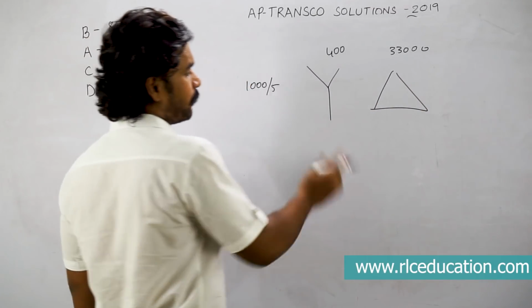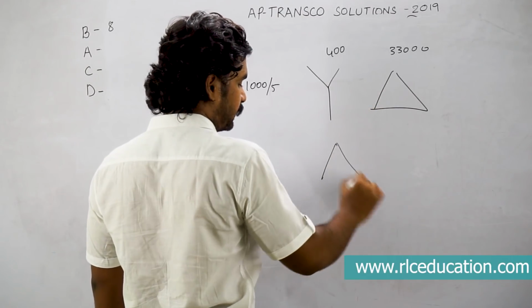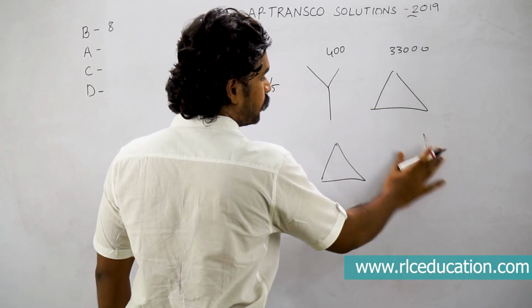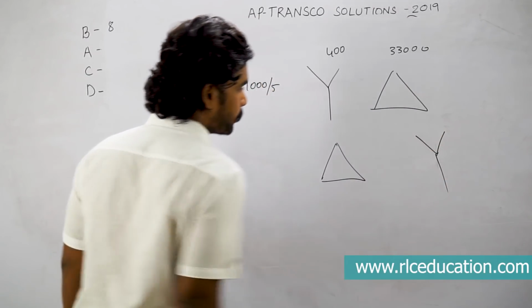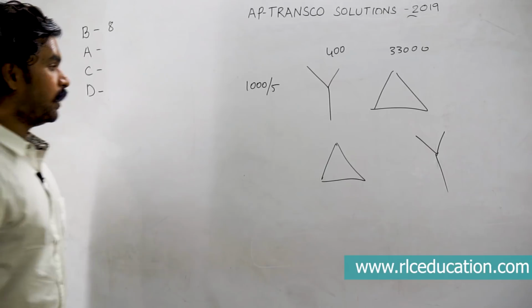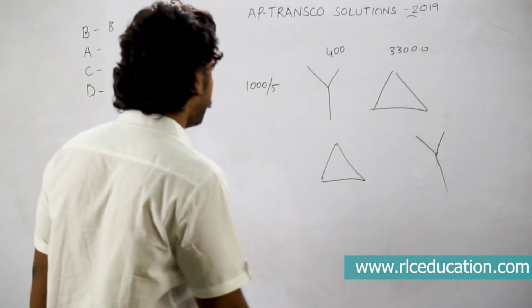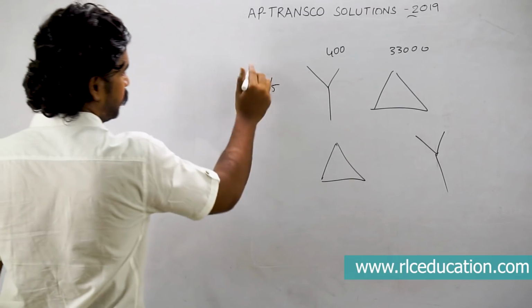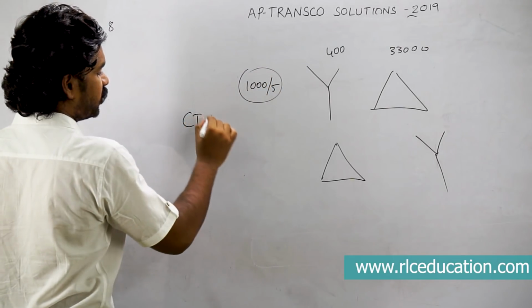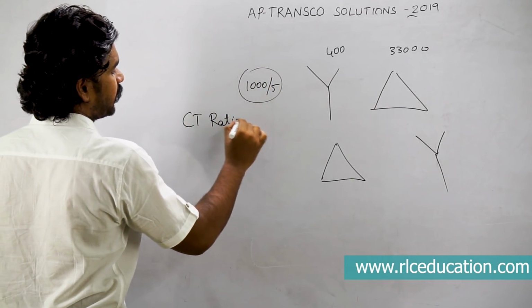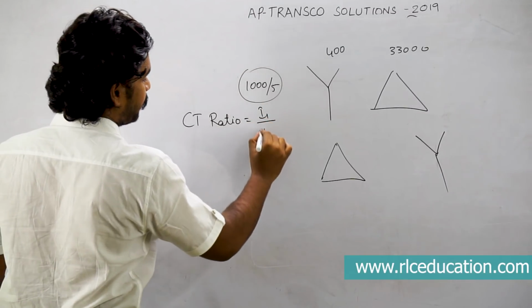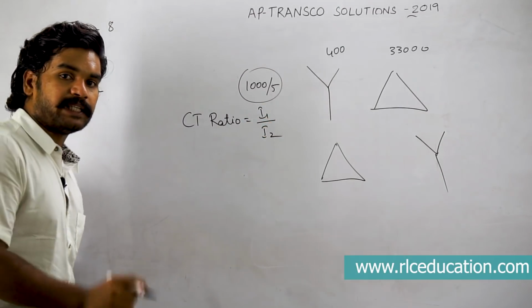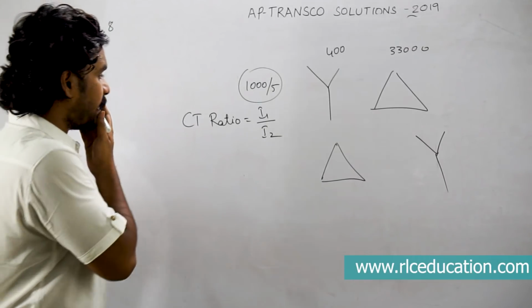So as you know, for differential protection, if star-delta is there, then the CT secondaries are connected in delta and star in this way, delta and star in this way. There is one important thing that you have to notice about the CT ratio. See, what is CT ratio? CT ratio is nothing but the primary CT current by secondary CT current.